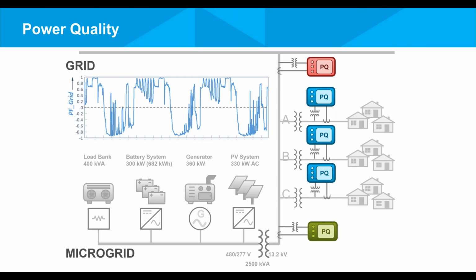in two scenarios. The first scenario is where the inverters are not set, or the microgrid is not set, to control the power factor locally. And then the second scenario is where the inverters are set to control the power factor. When the inverters are not set to control the power factor, this is what the power factor looks like. The objective is for the power factor to be as close to unity as possible, and that is where the generation is being operated efficiently.